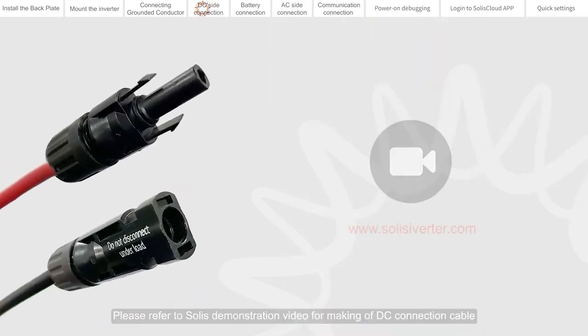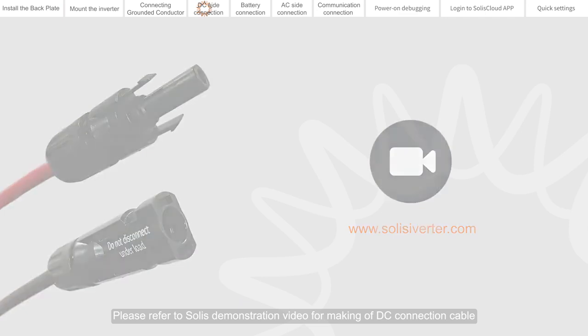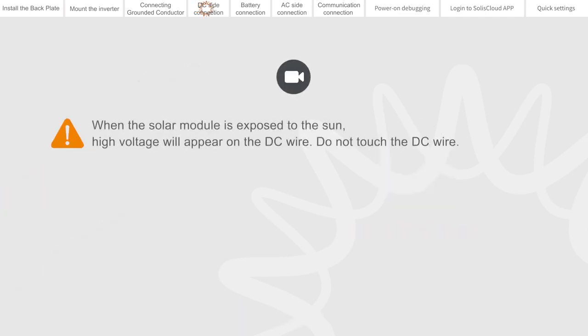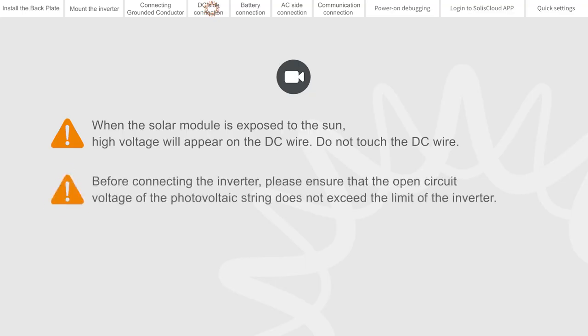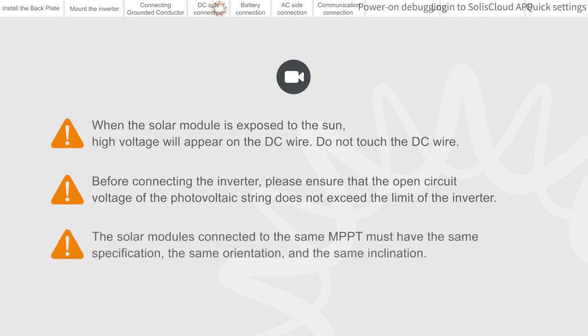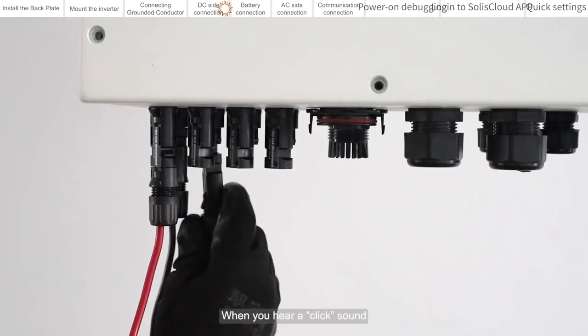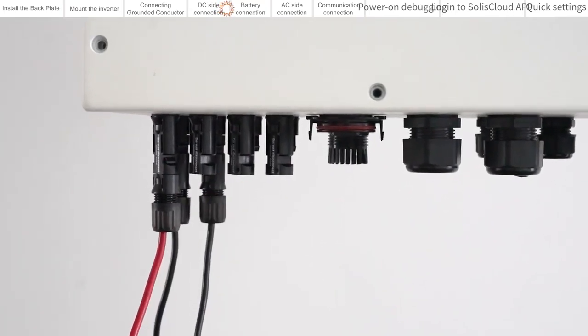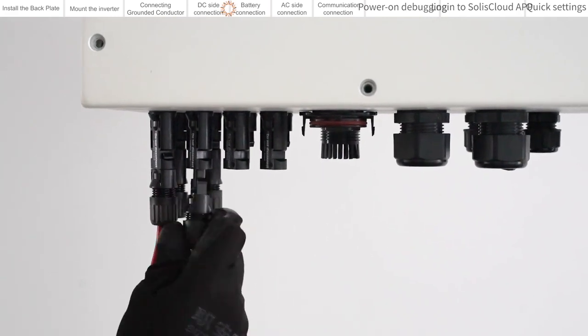Please refer to Solis demonstration video for making of DC connection cable. When the solar module is exposed to the sun, high voltage will appear on the DC wire. Do not touch the DC wire. Before connecting the inverter, please ensure that the open circuit voltage of the photovoltaic string does not exceed the limit of the inverter. The solar modules connected to the same MPPT must have the same specification, the same orientation, and the same inclination. When you hear a click sound, it indicates that the connection is fastened.